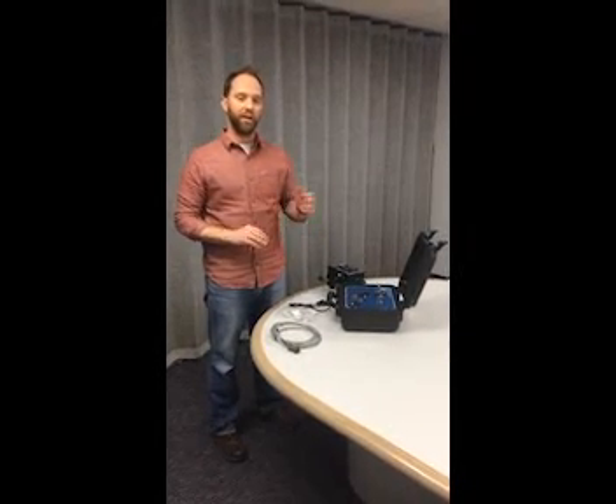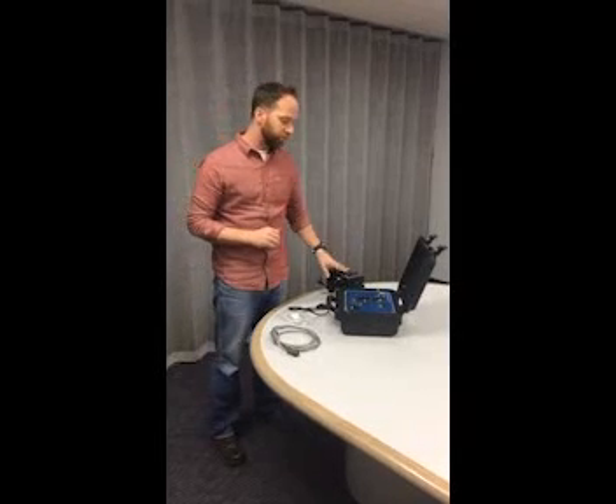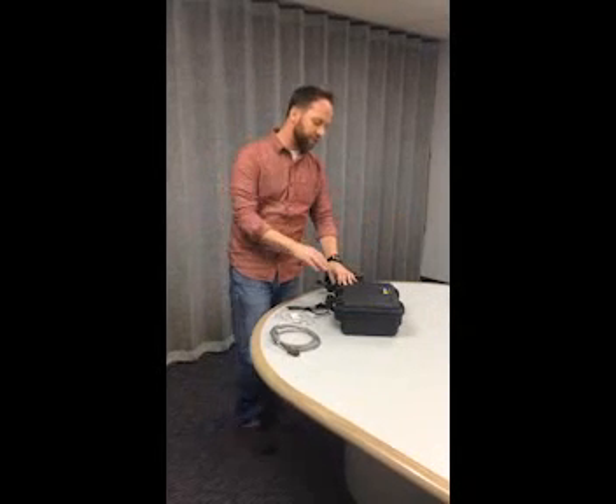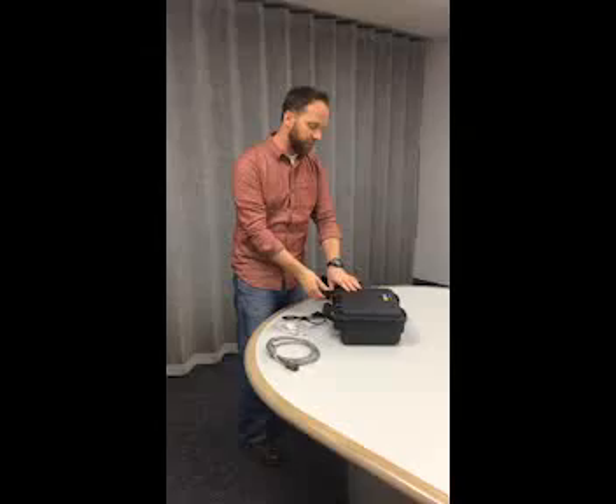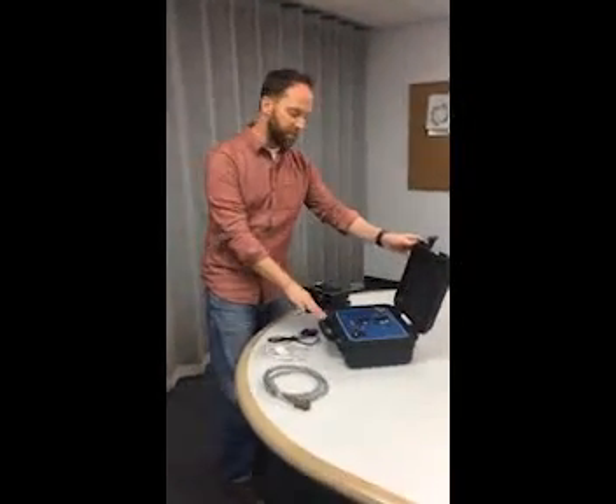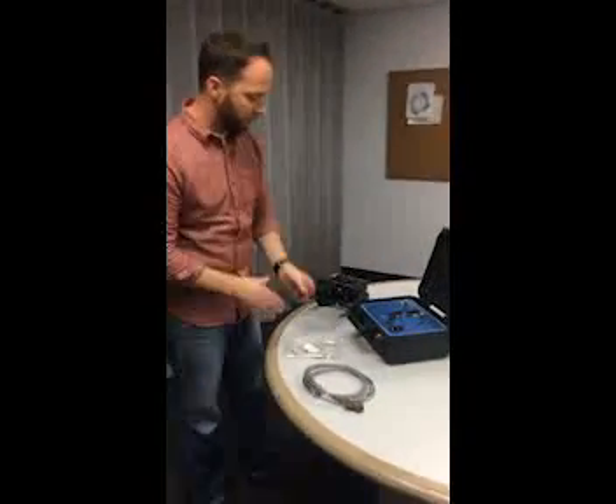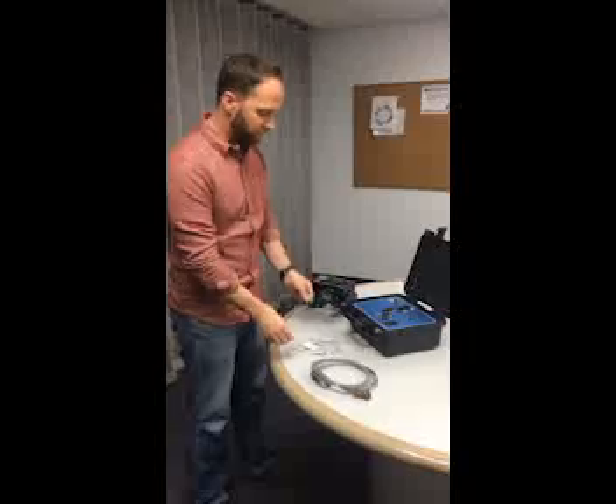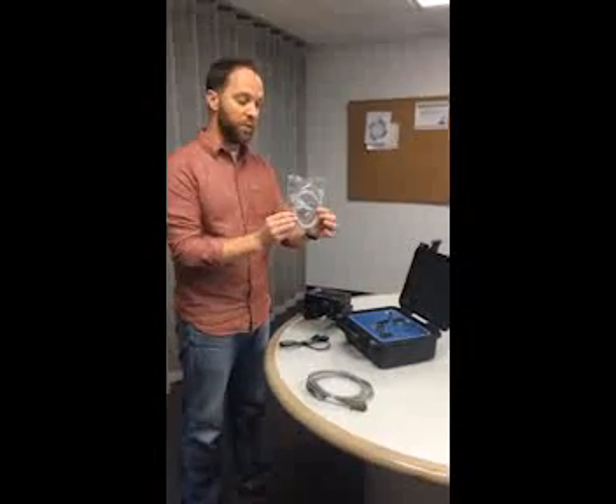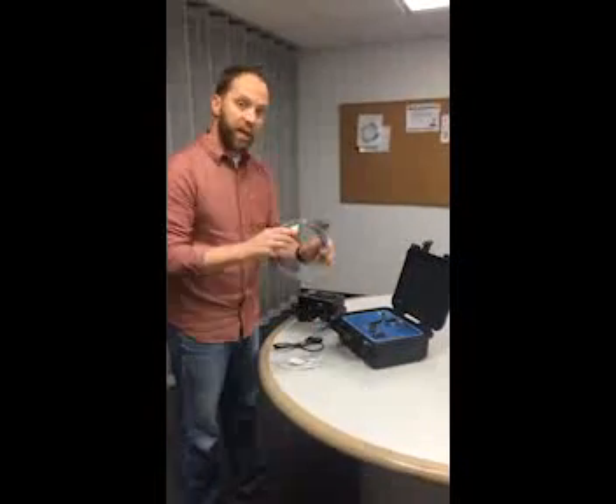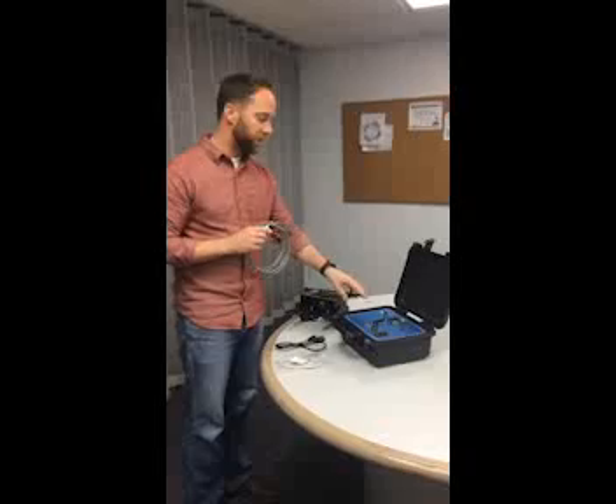Thank you for purchasing the FM50 test set. We want to walk through what comes in the kit, how to install it, and how to field calibrate your flow meter. What comes in the kit is your FM50 test set, which comes in this Pelican case, and we will walk through how to set it up. But you should also find your AC power cable, your male-to-male USB cable, and the cable that connects the FM50 flow meter to your test set.